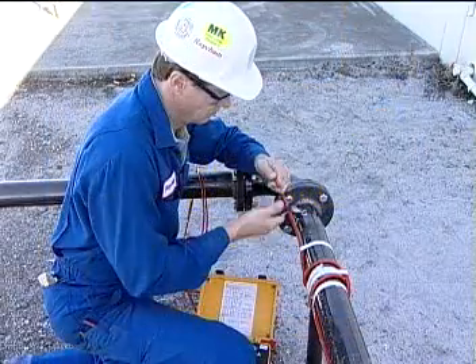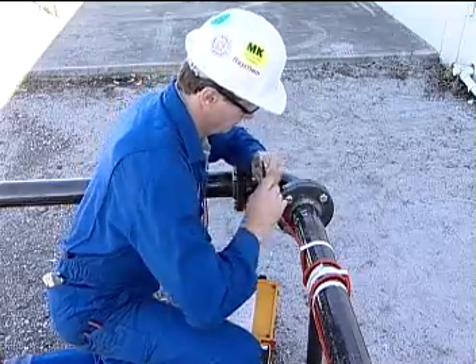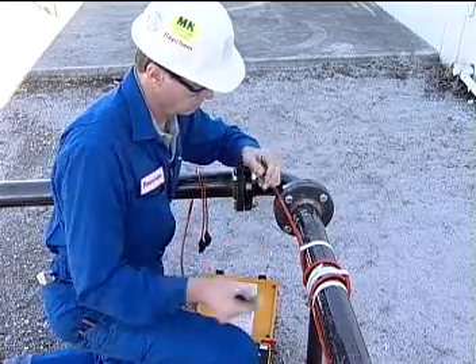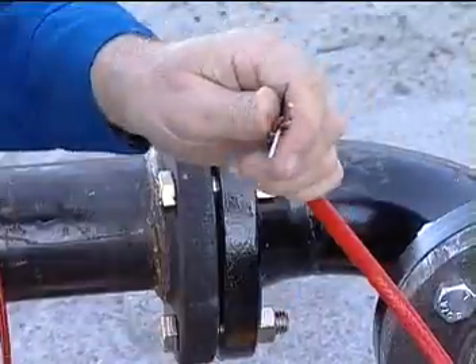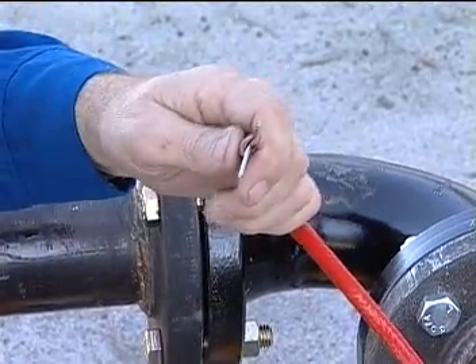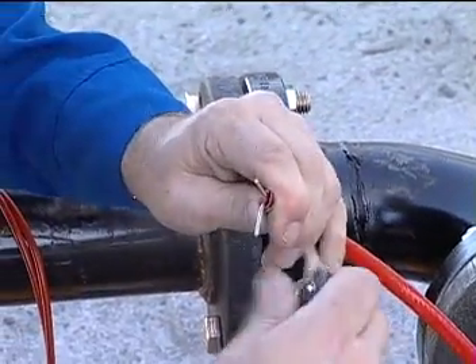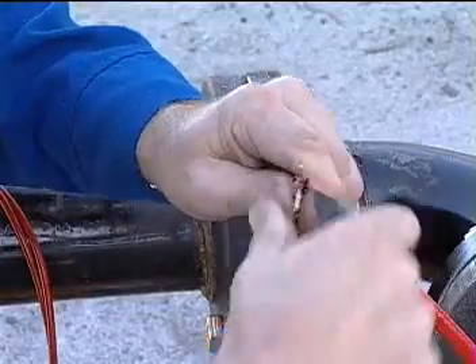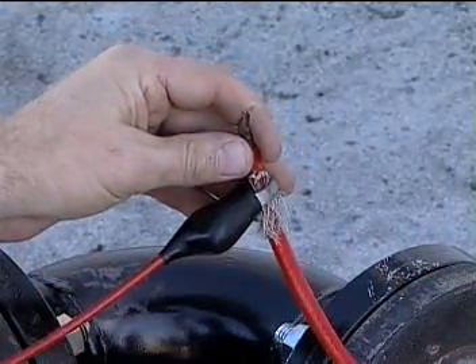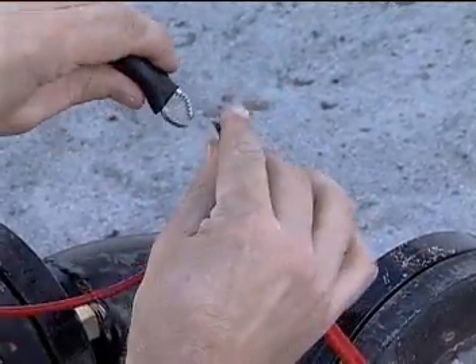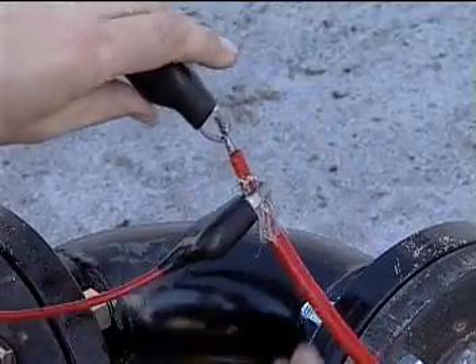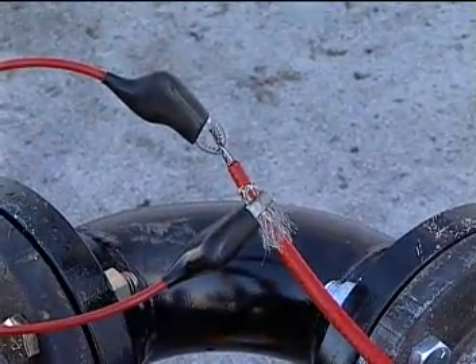2500 volts DC tester. To conduct an insulation resistance test of the cable, take the cable from the pipe and strip approximately 2 inches of the outer jacket from the cable. Then pull the braid back. Prepare the opposite end of the cable in the same way. Then attach one lead to the braid and one lead to the bus wire. Make sure that the exposed bus wires and braid never touch each other or the pipe.